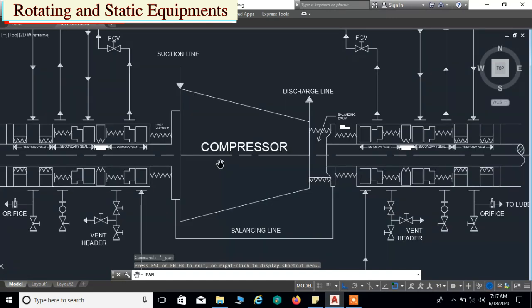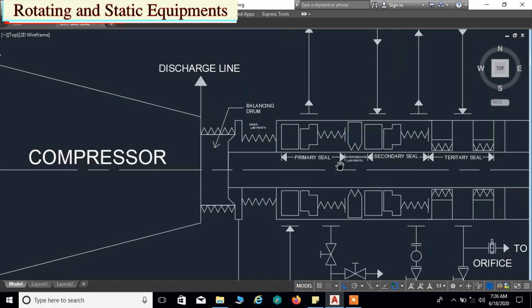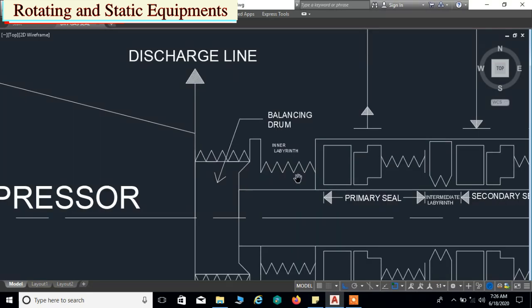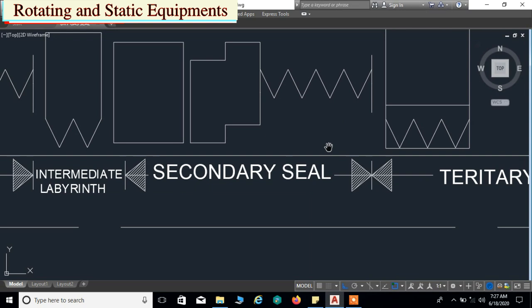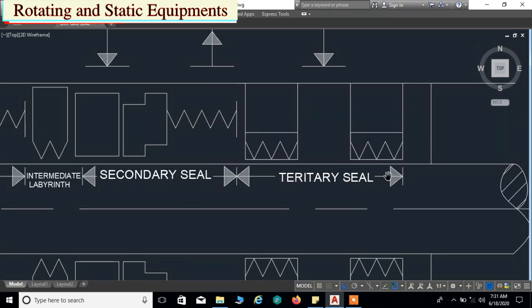These mechanical gas seal units are made as cartridge type seals with assembly bars. In order to prevent the process gas from escaping through the chambers and inner labyrinth seal, every individual chamber is pressurized by process gas or external source gases. For primary seals, process gas from the compressor final discharge is used — this is called seal gas. Initially, seal gas supplied from an external source is added to the process gas. For secondary seals, nitrogen gas is used as a buffer gas because it is inert and acts as a backup for the primary seal. For tertiary seals, instrument air is used for flushing.